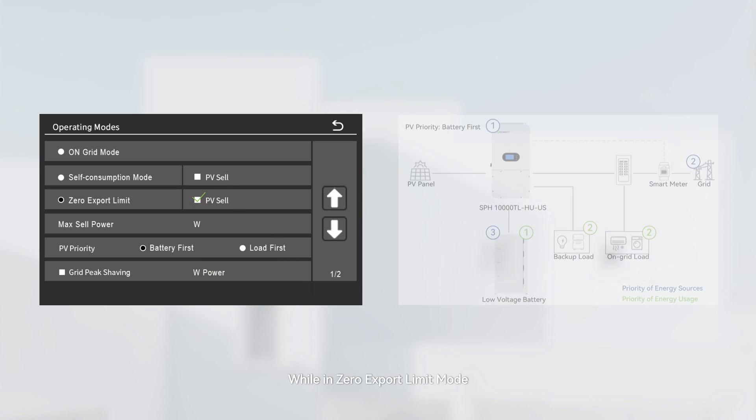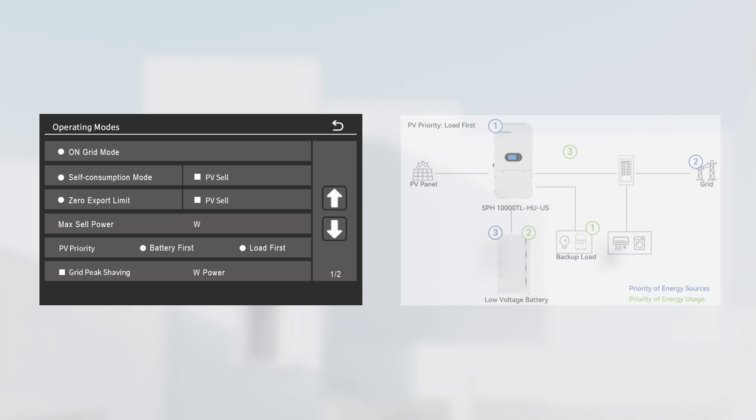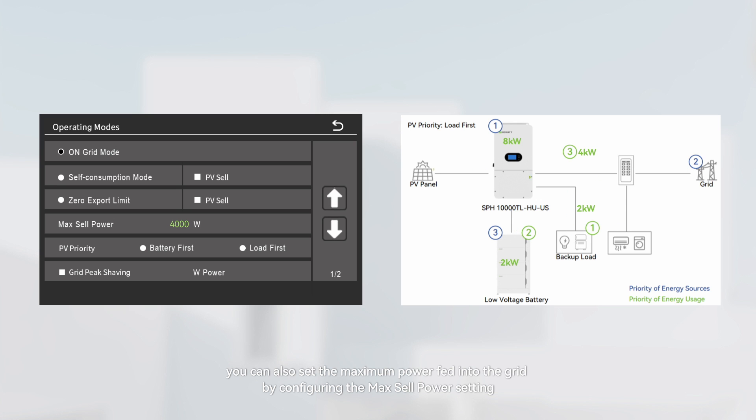While in zero-export limit mode, enabling the PV Sell function allows unrestricted generation of solar power, and the surplus solar power will be exported to the grid. When allowing excess PV power to be exported to the grid, you can also set the maximum power fed into the grid by configuring the Max Sell Power setting.